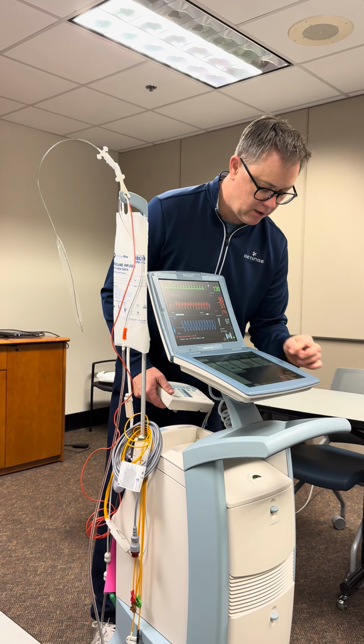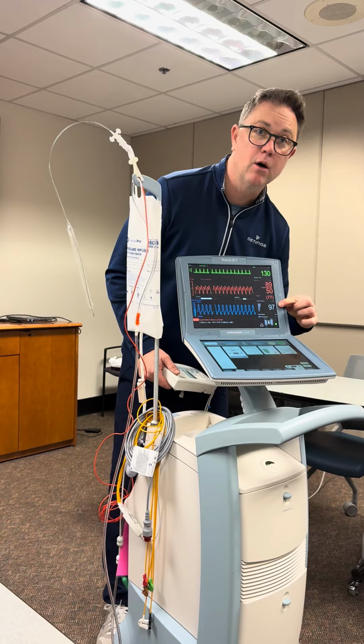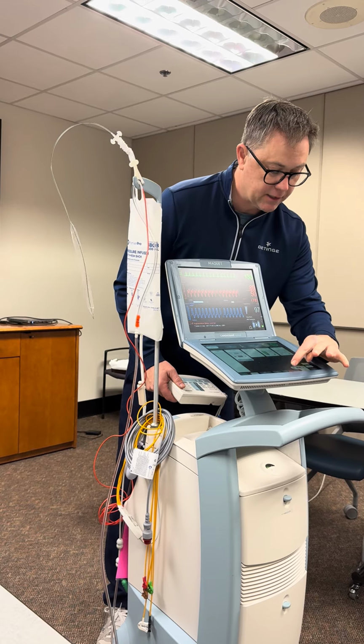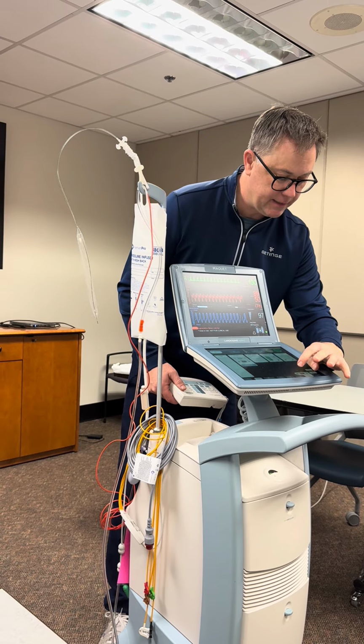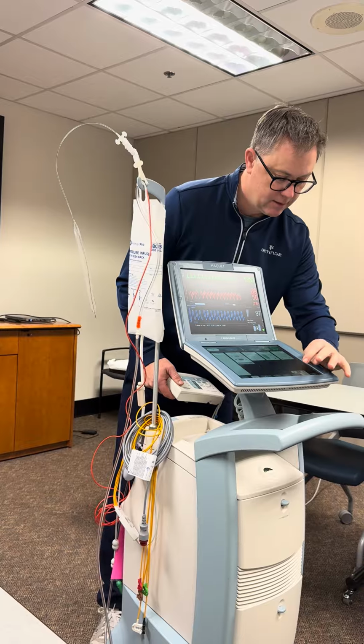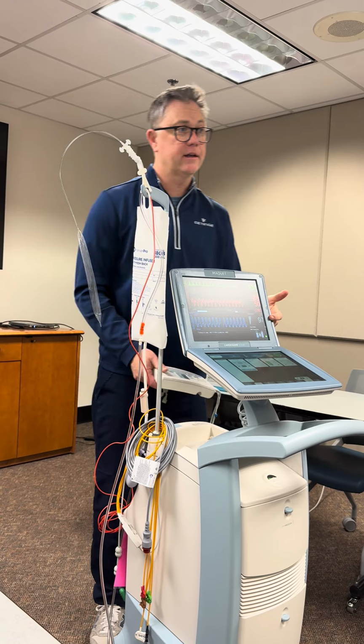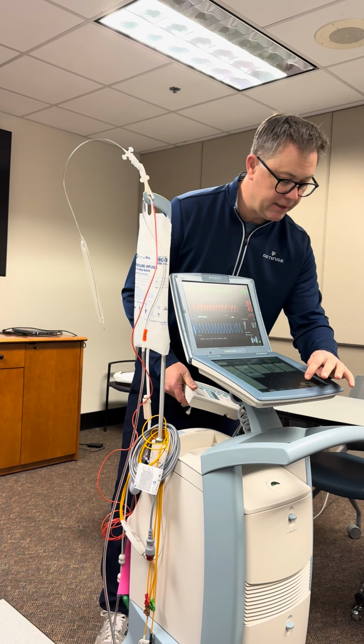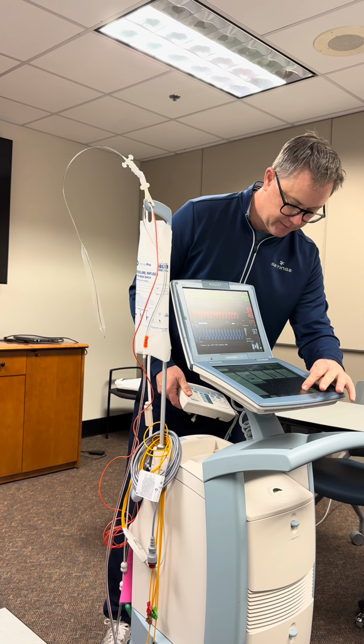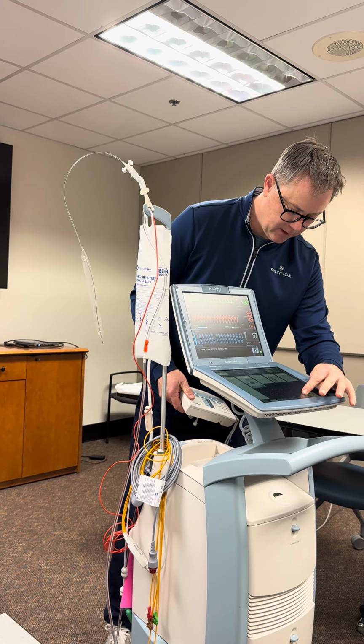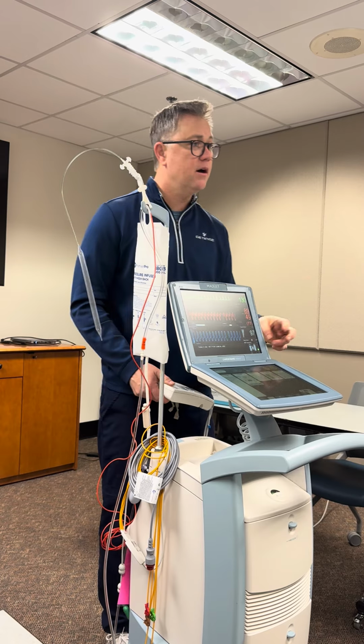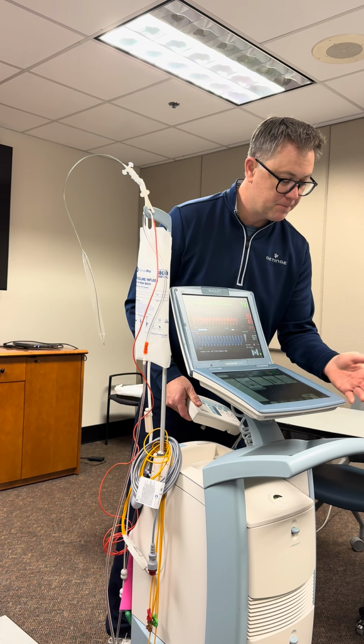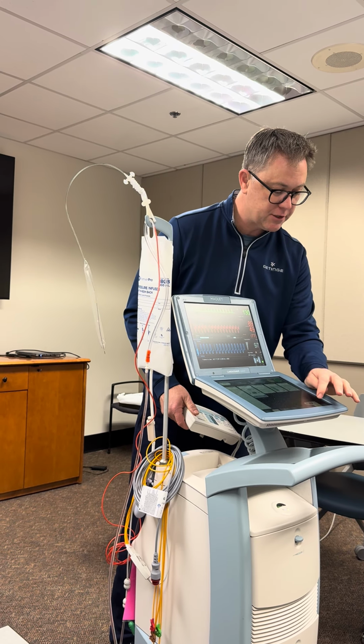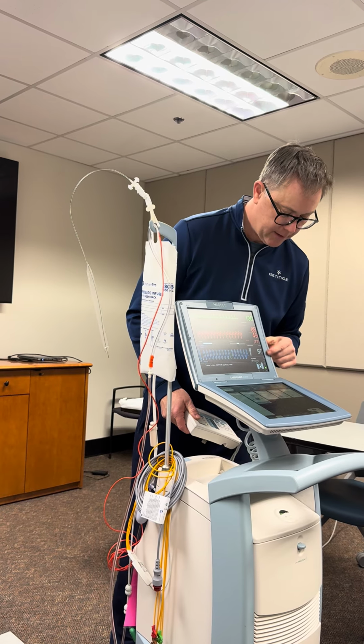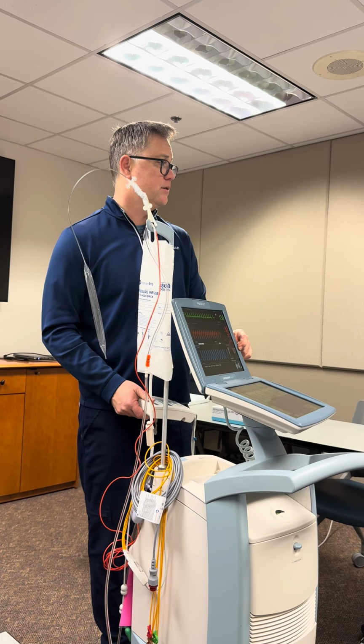That augmentation alarm, I'm going to lower it so we're roughly 10 below what we're currently augmenting. So I'm just going to knock it down to like 86. We're roughly 10 below and I've cleared that alarm. Some cath labs will come in here before the case and just turn this off, so you can turn it off as well. Augmentation alarm's off. And then when you're getting ready to deliver the patient to the ICU, if you just arrow up one time, it will automatically set it to 10 below. So that's another thing you can do.